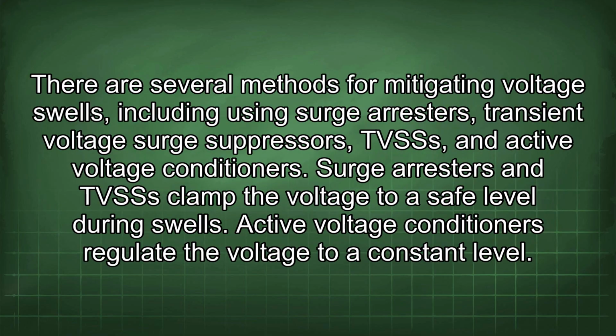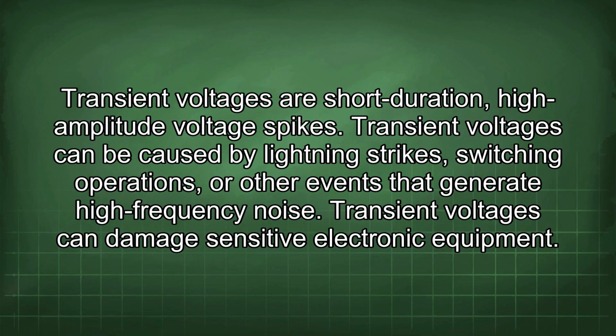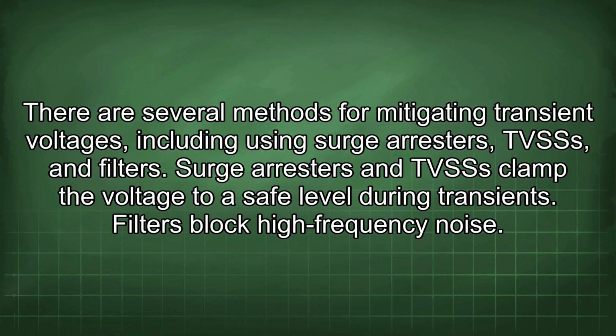There are several methods for mitigating voltage swells, including using surge arresters, transient voltage surge suppressors, TVSSs, and active voltage conditioners. Surge arresters and TVSSs clamp the voltage to a safe level during swells. Active voltage conditioners regulate the voltage to a constant level. Transient voltages are short-duration, high-amplitude voltage spikes. Transient voltages can be caused by lightning strikes, switching operations, or other events that generate high-frequency noise. Transient voltages can damage sensitive electronic equipment. There are several methods for mitigating transient voltages, including using surge arresters, TVSSs, and filters. Surge arresters and TVSSs clamp the voltage to a safe level during transients.